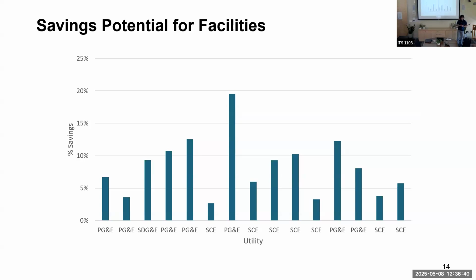And then we looked at around 15 or 16 different cold storage facilities in California in all PG&E, SDG&E, and SCE regions. And we just evaluated what energy savings we might come up with by shifting 100 kW out of that on-peak period and into the off-peak periods occurring before or after the on-peak period. So this is not even optimizing their operation. This is just looking at what happens if we just shift out 100 kW. And 100 kW for most of these facilities is like 10 or 20% of their load. Most of these facilities lie around maybe 500 kW of sustained load or around 1000 kW of sustained load.